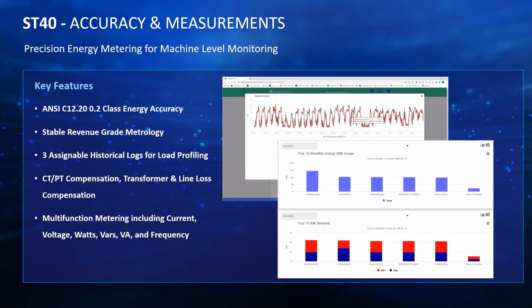We also have compensation built into the meter. We can compensate for accuracy loss at the low end of current transformers. We can also compensate for losses from a transformer in a line. So if you have this meter inside your building, 100 to 1,000 feet away from the revenue meter, we can calculate the losses of the line between the ST40 and the revenue meter and internally compensate for that loss, so that when you are comparing the ST40 with the revenue grade meter or your billing meter or your utilities meter, the values will match and you don't have to worry about those losses in between.